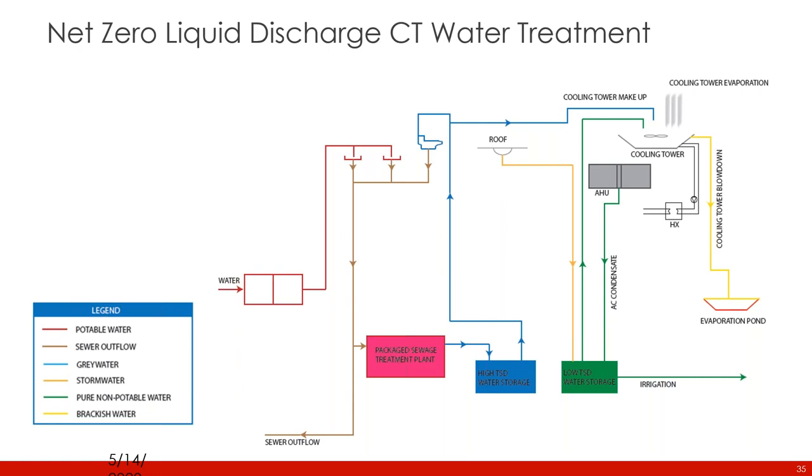And then the third major step is to control the silicate concentration of the water. So you want the silicate concentration in the water to be such that you form a very thin scale of silica on all the metallic surfaces to protect them from corrosion. And a number of facilities have successfully implemented this rather complex cooling tower water treatment regime, and they are able to achieve concentration ratios in their cooling tower of as much as 750 to 1,000 to 1.